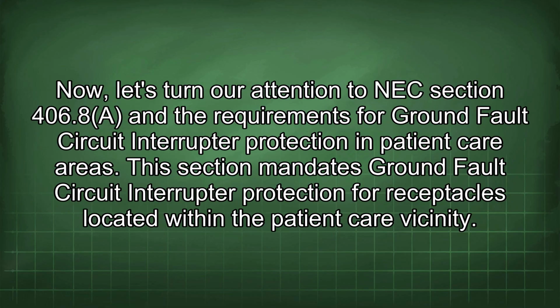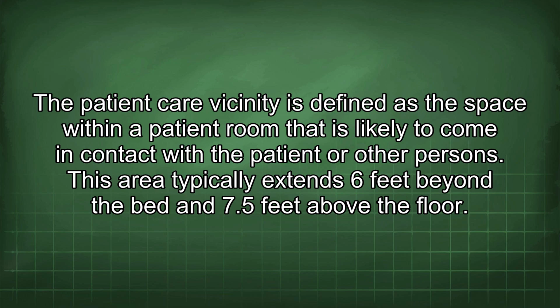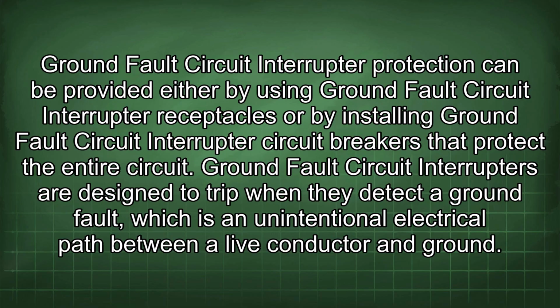Now, let's turn our attention to NEC Section 406.8 and the requirements for ground fault circuit interrupter protection in patient care areas. This section mandates ground fault circuit interrupter protection for receptacles located within the patient care vicinity. The patient care vicinity is defined as the space within a patient room that is likely to come in contact with the patient or other persons. This area typically extends 6 feet beyond the bed and 7.5 feet above the floor. Ground fault circuit interrupter protection can be provided either by using ground fault circuit interrupter receptacles or by installing ground fault circuit interrupter circuit breakers that protect the entire circuit.